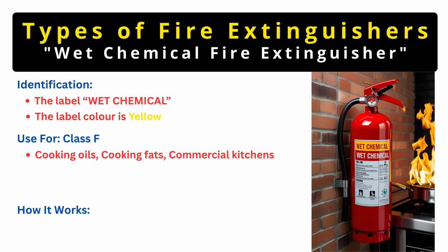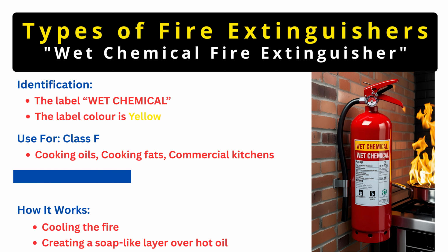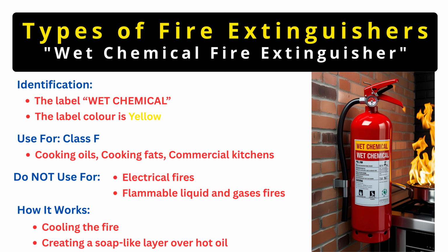Now let us understand how it works. Wet chemical extinguishers work by cooling the fire and creating a soap-like layer over hot oil. This process is called saponification, which prevents reignition. A wet chemical extinguisher must not be used for electrical fires, flammable liquid fires, flammable gas fires, or flammable metal fires.